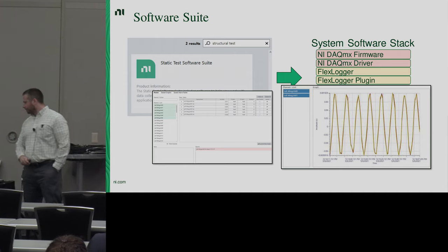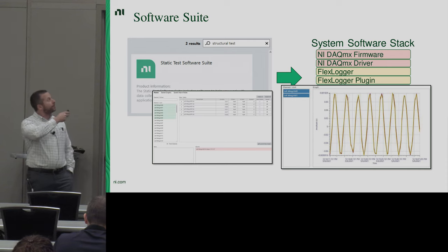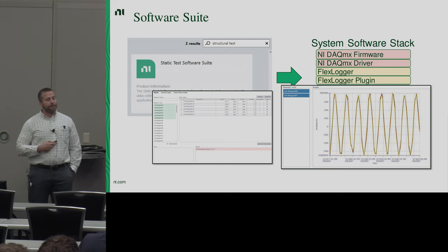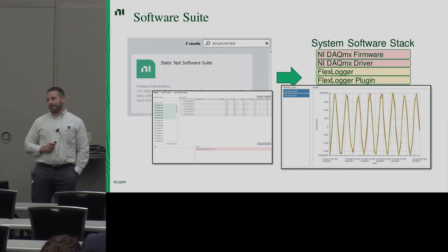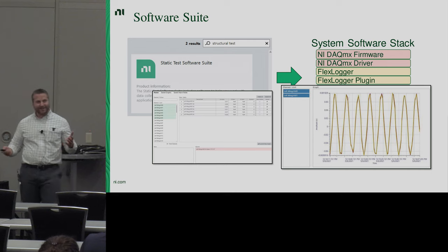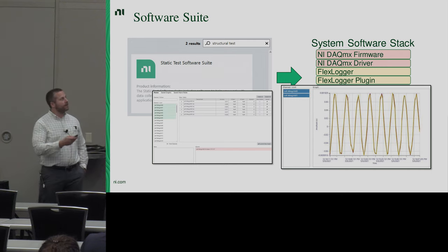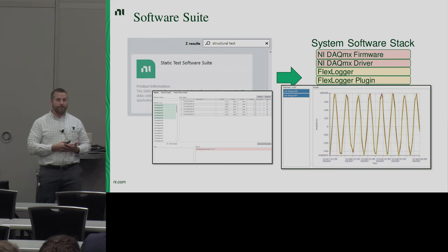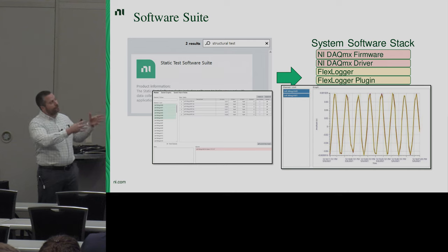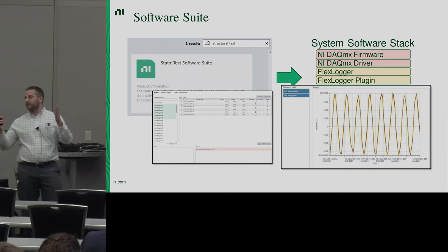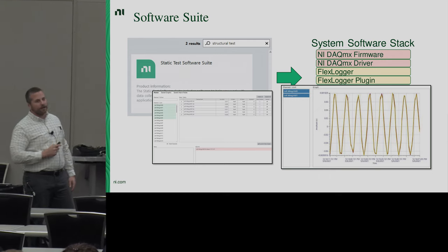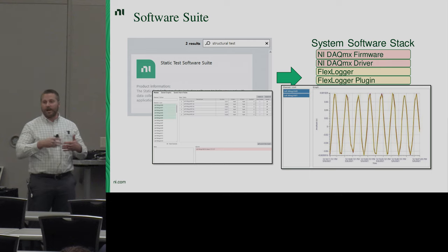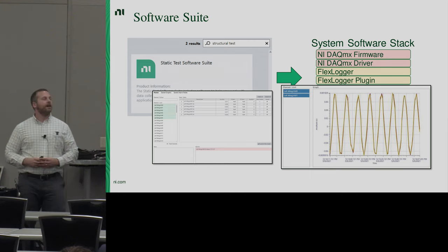If you open Package Manager and search 'structural test,' you'll find the Static Test Software Suite. Download it and you get DAQmx, FlexLogger, SystemLink, and a web application. The web application is hosted on the server — you open a browser, log into SystemLink with your username, and get a view of all channels in the system as reported by FlexLogger. You can select channels of interest and get live updates in a table of current values, create alarms against that data, and enter comments that show up in the FlexLogger log. You can select a subset of channels, hit Graph, and fill your screens with time history displays.